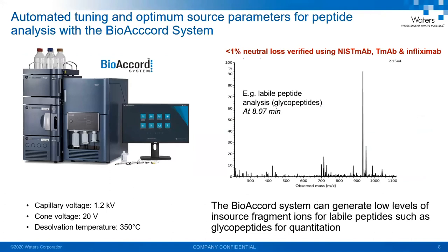The streamlined workflow method for peptide MAM starts with data acquisition using the BioAccord system. The BioAccord system addresses one of the biggest challenges of peptide analysis — in-source fragmentation or source-induced modifications. The auto-tune parameters, coupled with the generic source settings, managed to reduce source-induced fragmentation of glycopeptides of NISTmAb digest down to less than 1%. We verified these results in trastuzumab digest as well as in infliximab digest.